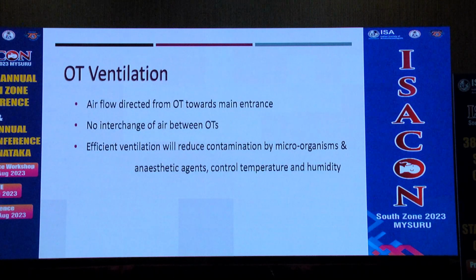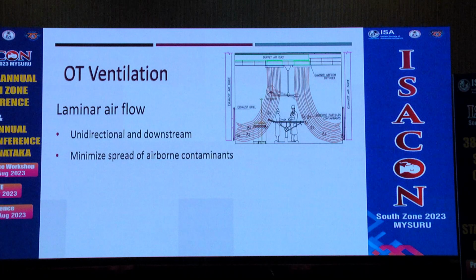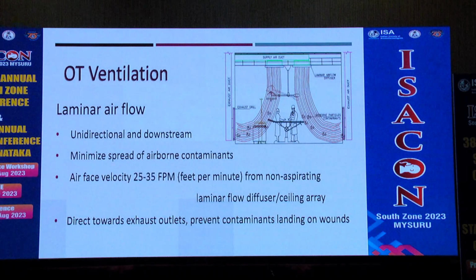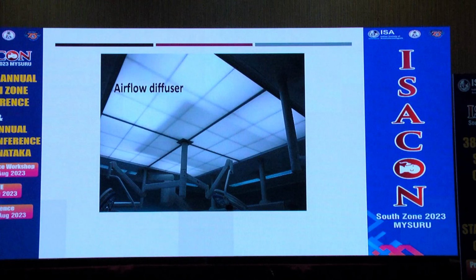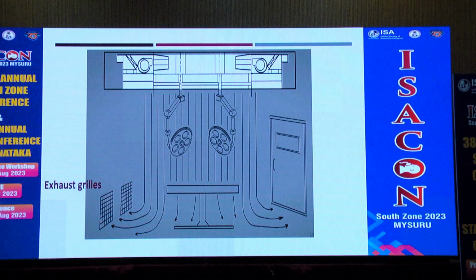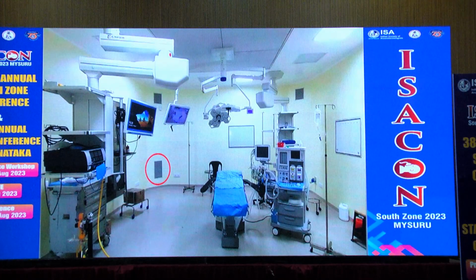For ventilation, the airflow should be directed from the OT towards the main entrance, and there should not be any air exchange between the OTs. Effective ventilation will reduce contamination by microorganisms and anesthetic agents and control temperature and humidity. Laminar flow is unidirectional and downstream, and minimizes the spread of airborne contamination. It is directed from the ceiling array to the exhaust outlet. These are the airflow diffusers from the ceiling, and this laminar flow is directed towards the exhaust. These are the exhaust grills.